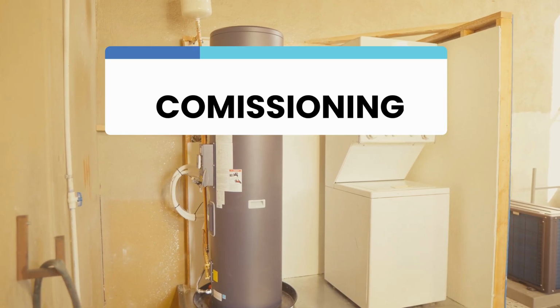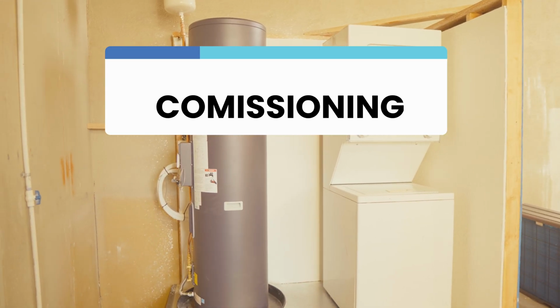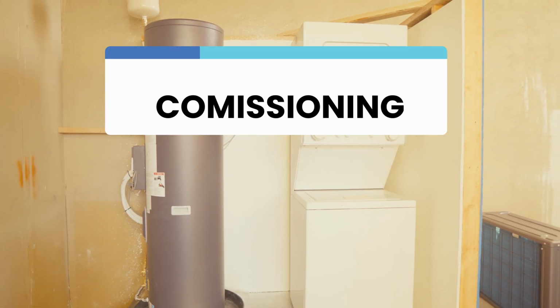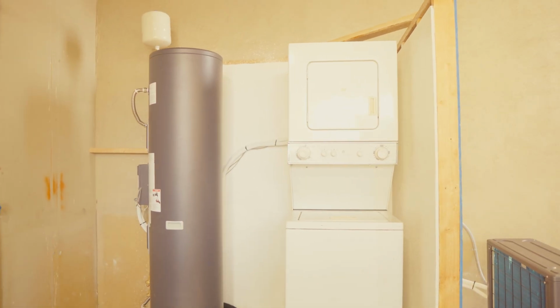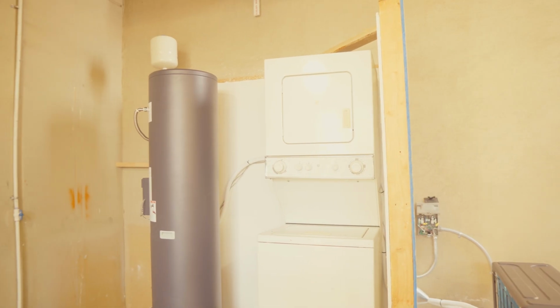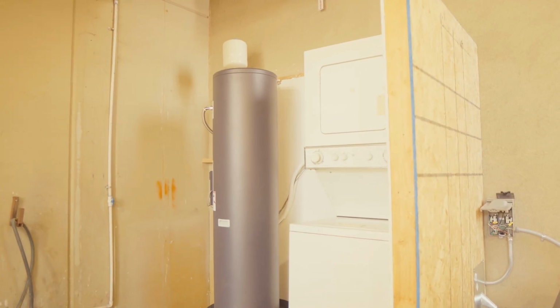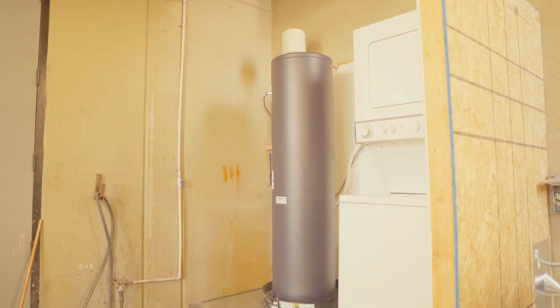Once all components are installed and you have followed the manual and all safety steps carefully, you can now prepare to power on the unit. As an important precaution, make sure the water tank is completely filled before turning on the system. Powering the unit without water in the tank can cause serious damage.